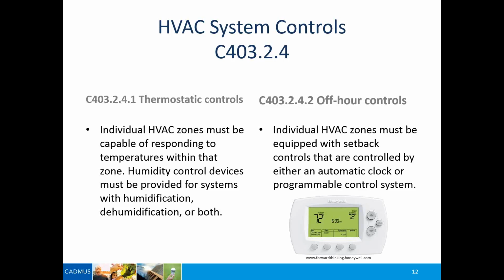For a lot of the systems that are going in right now, they seem to be a lot of single zone unitary types of systems, package air conditioners. And so the single zone systems, the control requirements on those are fairly simple and almost look like a residential scale type of control. The first one is making sure that you have a thermostatic control. If you have humidity controls, you need to be able to control the humidity.